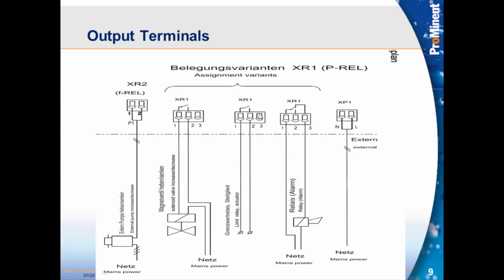Here, the center option for XR1, it's being used more as a limit relay. So we can program that limit. That limit will give you 2 different points of reference on that. So the limit will trip to a low point as well as a high point. So you don't know necessarily if you're over range or under range, but you know that that limit or your range has been exceeded one way or the other when that is actuated. If you're only going to take advantage of one of those limits, you can make the other one just to the very upper end of that measuring range to sort of eliminate it.